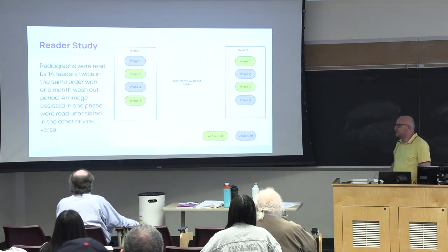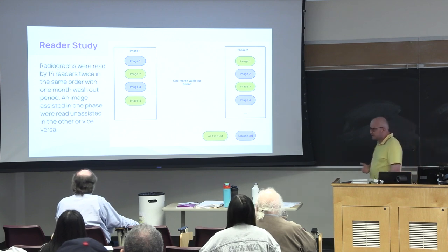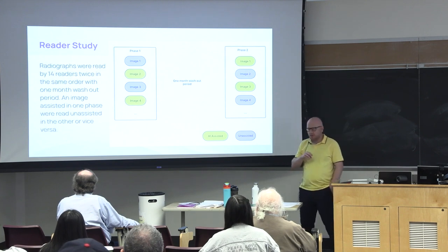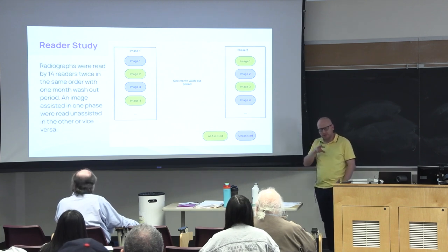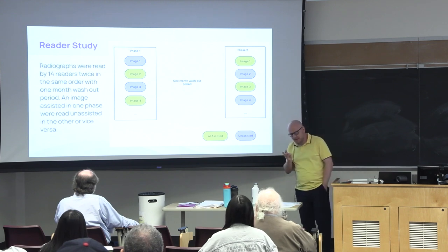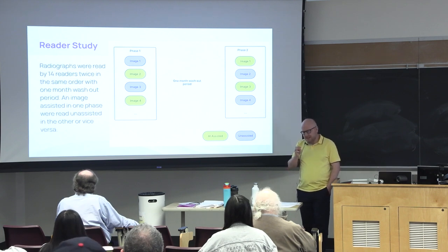How do we run an FDA study? This is an FDA 510(k) CADe device. All device clearances have their differences, so this may not necessarily be the same for all the other applications that you will see, but for this application it is. It's a second read. Second read means when you have the finding, the doctor still sees the X-ray as is without any overlay first.